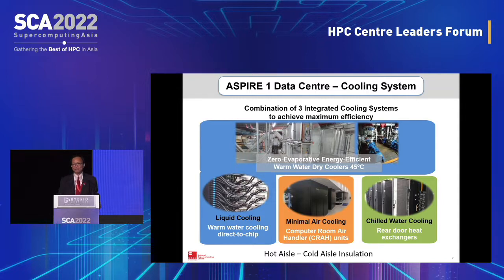This combination of 3 integrated cooling systems comprises a warm water direct-to-chip cooling system, 40 degrees in and 45 degrees out, combined with a rear door heat exchanger tapping on the chilled air conditioning cooling system of our office block. With minimum air conditioning cooling, we're able to achieve that level of efficiency, 1.08 on a good day.